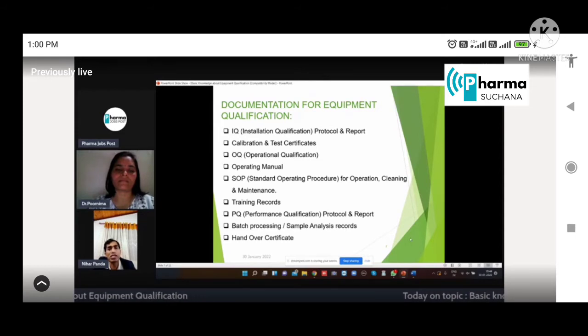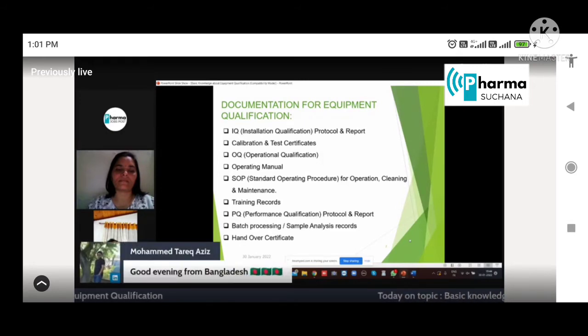Even the various test certificates, maybe hydro test or other tests, those test certificates are also to be provided by the manufacturer. Next is OQ, operational qualification. After completion of the IQ, during IQ, many other things are required, like space where it is to be installed, what utilities are required, and how much working space is required. After that, OQ can be done.